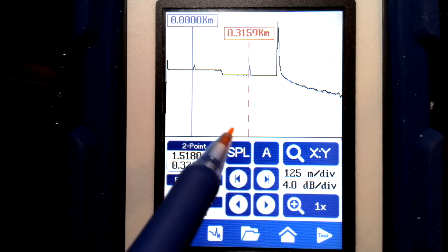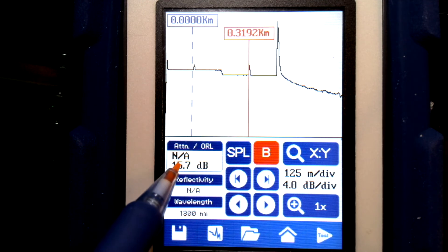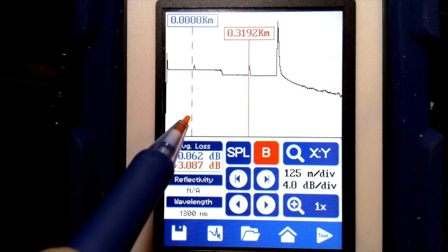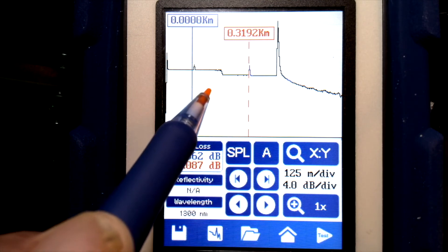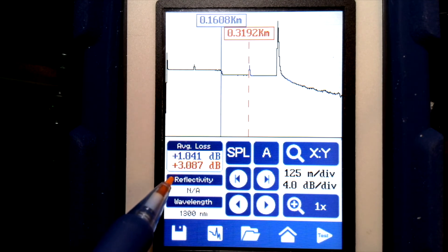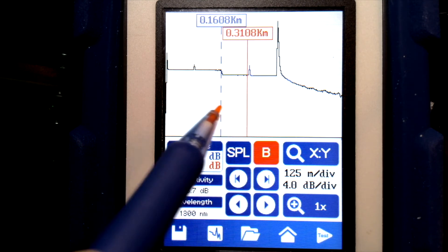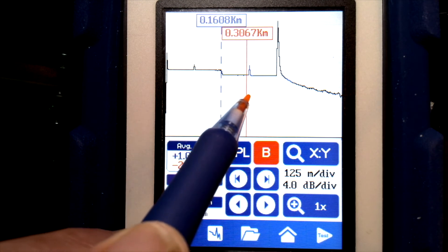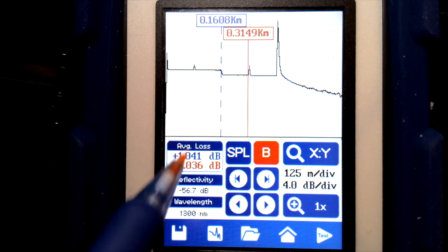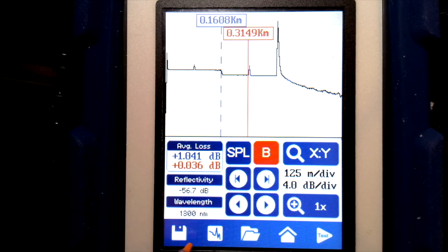I can toggle between my A and B cursor — the active cursor is solid. I can choose between the measurement types, and it shows a blue and a red number giving the loss for each cursor. If I put the A cursor on that splice, it's showing a loss of about 1 dB. If I move cursor B to this connector, it's showing a loss of about 0.03 dB for that connection. That's a quick overview of how the trace screen looks.